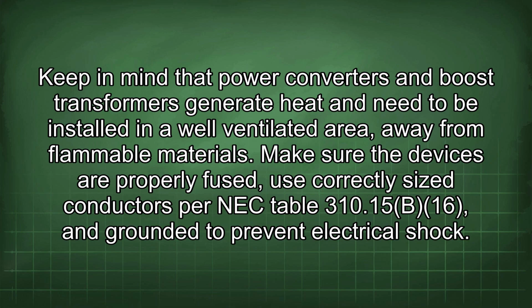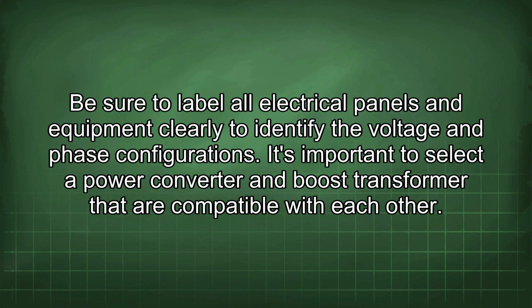Keep in mind that power converters and boost transformers generate heat and need to be installed in a well-ventilated area, away from flammable materials. Make sure the devices are properly fused. Use correctly sized conductors per NEC table 310.15(B)(16) and grounded to prevent electrical shock. Be sure to label all electrical panels and equipment clearly to identify the voltage and phase configurations.